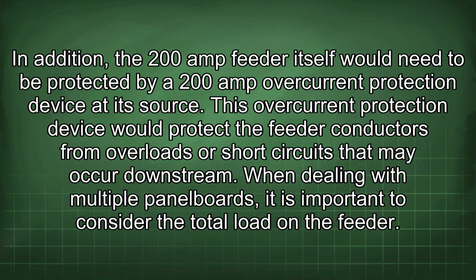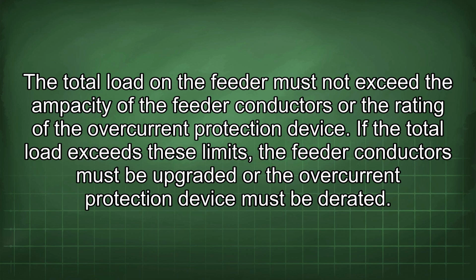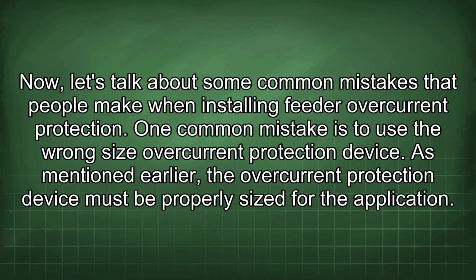In addition, the 200 amp feeder itself would need to be protected by a 200 amp overcurrent protection device at its source. This overcurrent protection device would protect the feeder conductors from overloads or short circuits that may occur downstream. When dealing with multiple panel boards, it is important to consider the total load on the feeder. The total load on the feeder must not exceed the ampacity of the feeder conductors or the rating of the overcurrent protection device. If the total load exceeds these limits, the feeder conductors must be upgraded or the overcurrent protection device must be derated. Now let's talk about some common mistakes that people make when installing feeder overcurrent protection.